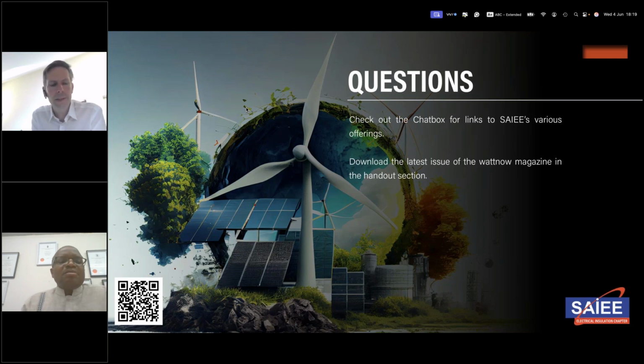And if I may add, because I forgot to mention something - of course there are also alternative solutions available which don't use fluorinated compounds. One vendor offers vacuum circuit breakers combined with high pressure air insulation. And for air insulated switchgear, I know a solution purely based on CO2-O2 mixtures, so without the C4 components. So in this discussion, I think one has to mention this when it's about PFAS and the fluorinated gases.